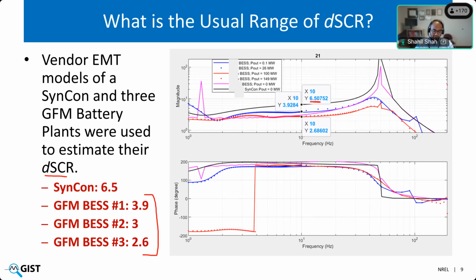The second major reason for this is that we are looking for grid strength from a grid forming resource. And it might be possible that some IBRs need grid strength support only for reactive power or basically voltage control. So by dissecting these two different performance metrics, active power response and reactive power response, we can have flexibility in having a higher Q by V scan gain, basically higher grid strength contribution in that axis compared to the active power, which again, if we talk about resources which don't have storage, we can still leverage that. So that is another reason why not just use simple impedance, but also look at these other scans which are looking at active and reactive power response separately.